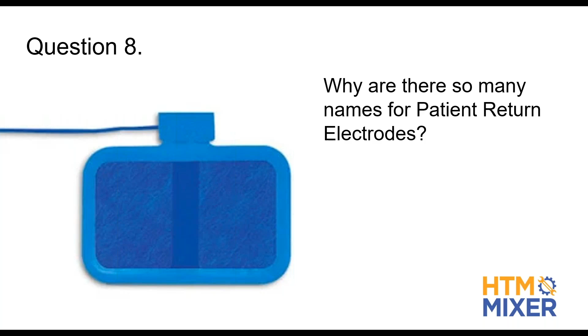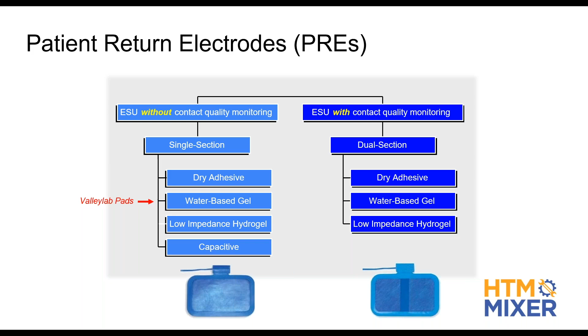We can divide those into two types of pads: a single section pad with no protection, where someone can get burned, or a dual section pad. They're made different ways — dry adhesive, water-based gels. The Valley Lab pads are made from a water-based gel, meaning they have 50% water in the gel, which is very good for conduction — and that's what you want when doing electrosurgery.